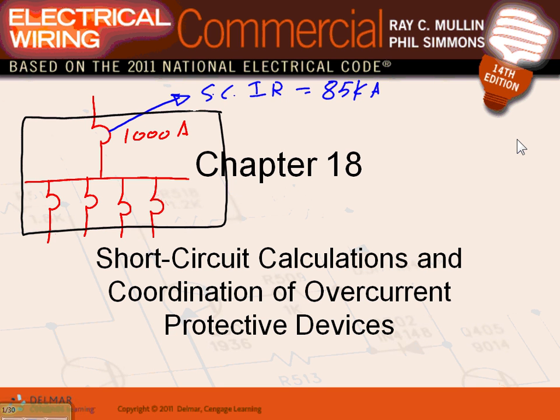The second value, guys, withstand rating. The switchgear has something called short circuit withstand rating. The withstand rating is how much the copper inside the panel can handle the mechanical stress because of the short circuit and the heat. Does that make sense? How much this panel can withstand heat and magnetic force created by the short circuit. So that's called withstand rating.